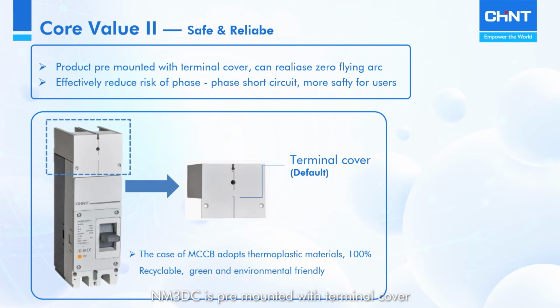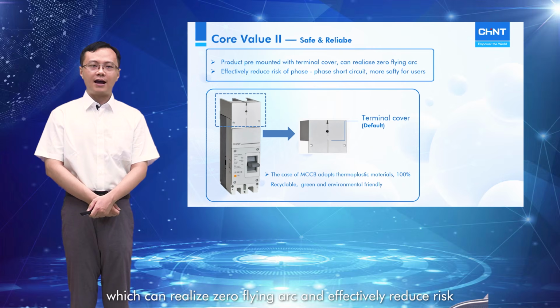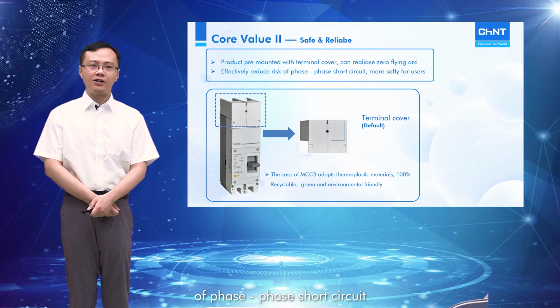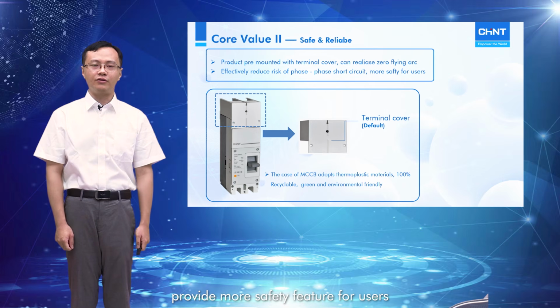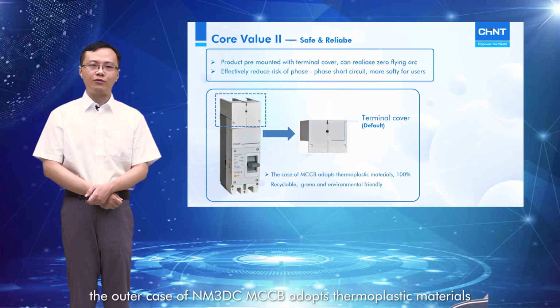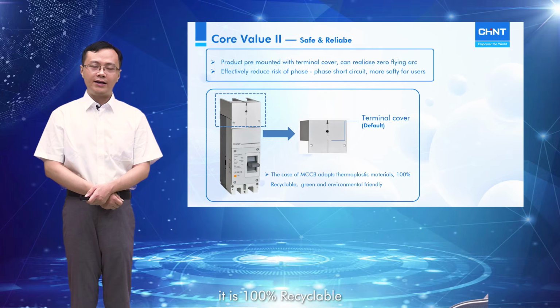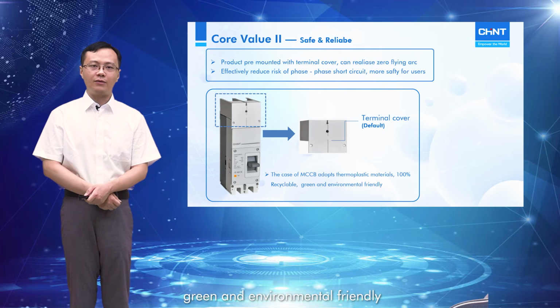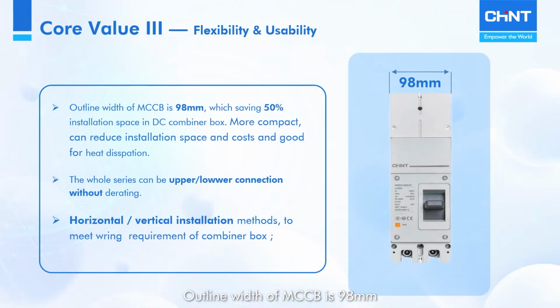NM3DC is pre-mounted with a terminal cover, which can realize zero flying arc and effectively reduce the risk of phase-to-phase short circuit, providing more safety features for the user. Besides, the outer case of the NM3DC MCCB adopts thermoplastic material. It is 100% recyclable, green, and environmentally friendly. The outline width of the MCCB is only 98 mm, which saves about 50% installation space in the DC combiner box. The compact size can effectively reduce installation space and cost, and is also good for heat dissipation. The whole series can be connected upper or lower and supports horizontal or vertical installation without derating, which extends the flexibility to be installed in a combiner box.